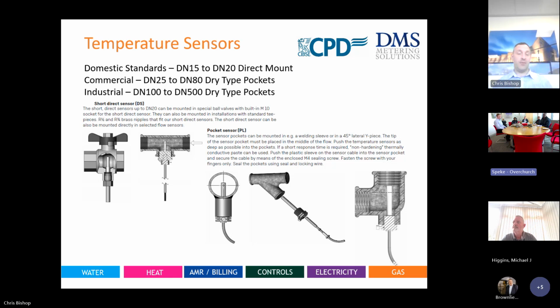And yet again, just that example there, the pocket must be touching the flow of water to abide by MID. So it must be designed in a way that you're not designing a bush that's, let's say, 100 millimeters out of the pipework, and you've only got a 34 millimeter pocket going into a 100 millimeter bush.